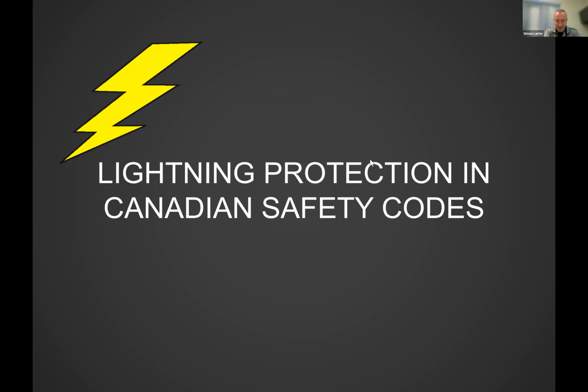Oh, neighbor's house, lightning damage, right by the gas meter. No, we don't accept galvanized ground rods for the grounding electrode because those will deteriorate too quickly, Ed. Galvanized steel for ground rod, I think it used to be allowed under the old CSA code, but we no longer accept it because they are just going to rust away too fast. And iron oxide is not particularly conductive, so the less conductivity we have in contact with the earth, the less efficient the dissipation of lightning current.